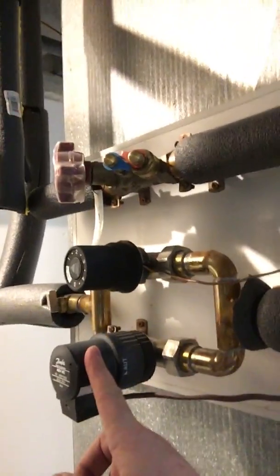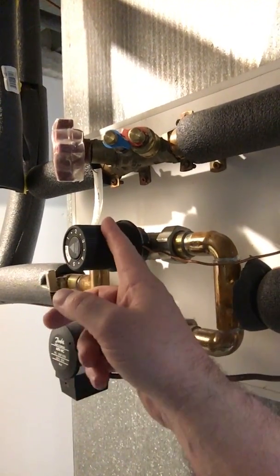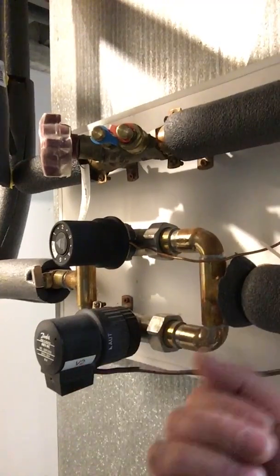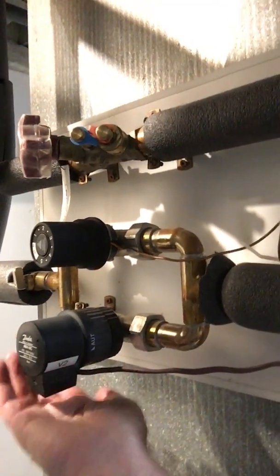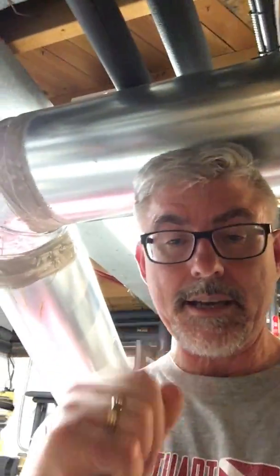So when we do get down to minus 40 and the radiant wall can't quite keep up, then we use this valve here to bypass this control. So what happens, this is regulating discharge air. Second stage says, hey, first stage radiant wall is not quite keeping up, so let's activate this, open this up, let water flow through into the coil, and then that of course provides high temperature air. High temperature, I say probably 140 degrees maximum we ever use, out into the space. So first stage radiant, second stage is the air. We use the fan coil for humidification and also filtration. So it's a beautiful, beautiful combination of thermal comfort and indoor air quality.